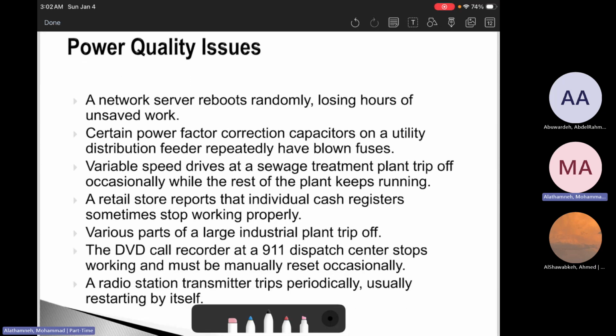Okay, let's go through a few hidden causes. The first one: a server reboots randomly. This is a classic voltage sag or momentary interruption. Servers are sensitive unless they have a UPS, which is an uninterruptible power supply. Even with a UPS, if the transfer isn't fast enough or the UPS is undersized, they can still reboot. So a server can reboot randomly.